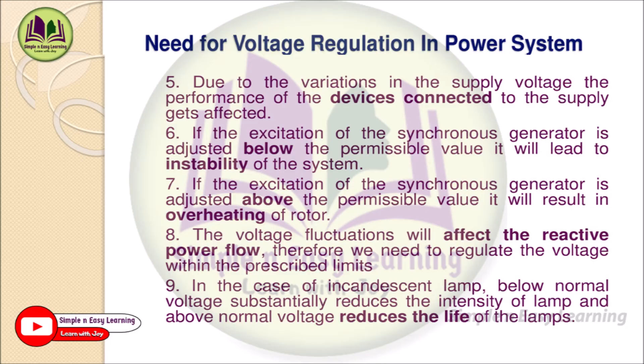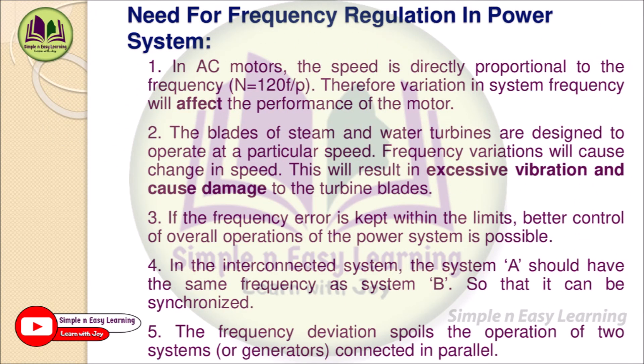Regarding the need for frequency regulation in power systems: First, in AC motors, speed is directly proportional to frequency — N = 120F / P — so variation in system frequency directly affects motor performance. Second, the blades of steam and water turbines are designed to operate at a particular speed; frequency variation causes speed changes, resulting in excessive vibration and damage to turbine blades.